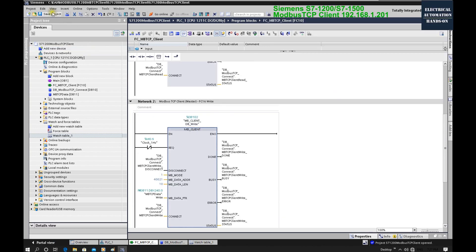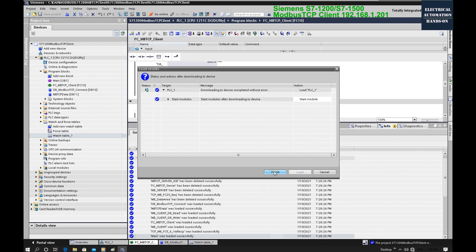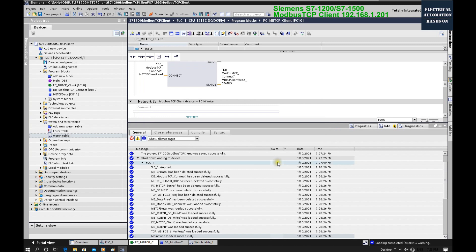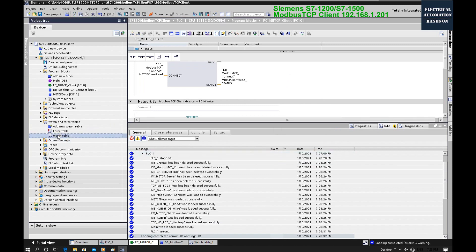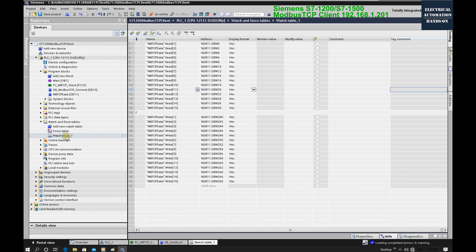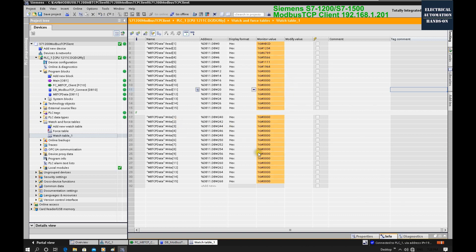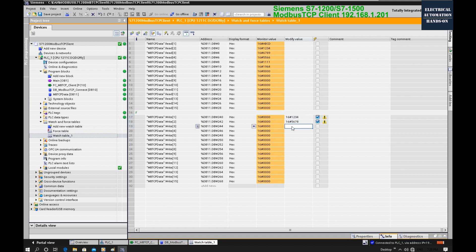Now let's download the program to the PLC and start the controller after the download. From the watch table, we can open and turn on monitoring. Let's write some test data in hex: for example, 0x1234 for the first register, 0x5678 for the next, and 0xAABB for the third. We send this data into the write buffer, and the second Modbus function block will write those values to the Modbus server side.